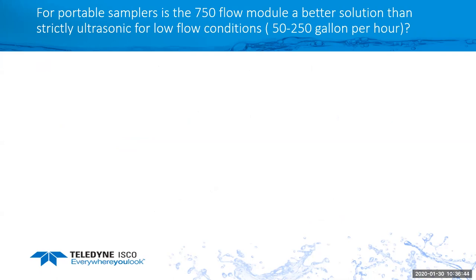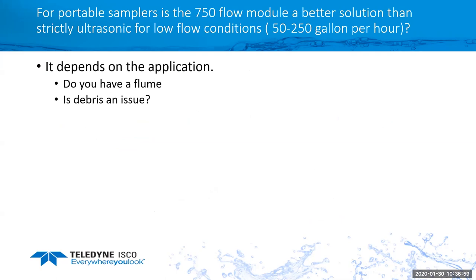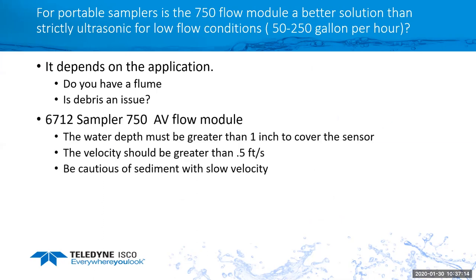All right, for the portable samplers, the question is, is the 750 module a better solution than strictly ultrasonic when they have flow conditions of 50 to 250 gallons per hour? It kind of depends on the application. If you already have a flume in place or if debris is an issue, flumes are highly accurate and have been used for a long time, so the ultrasonic may be a better option. But if you have a flume application and it's been known to surcharge, using level only would not be ideal, because the flume assumes or expects the flow to go one direction, so it would not be able to read reverse flow. In that case, an area velocity sensor like the 750 would be better.